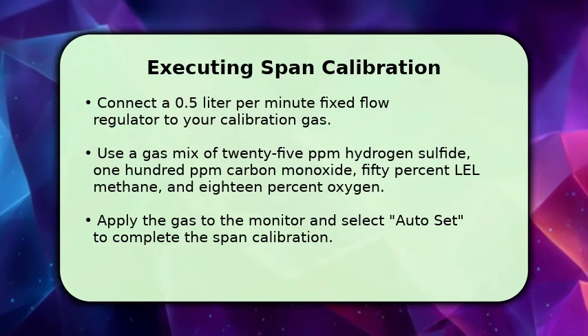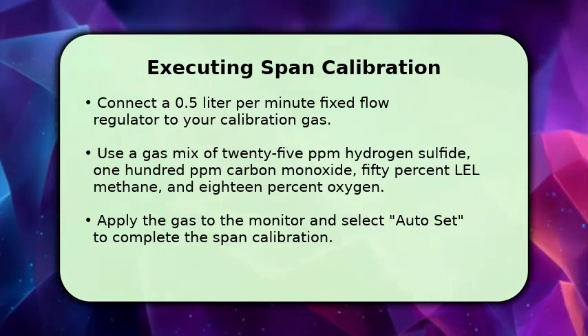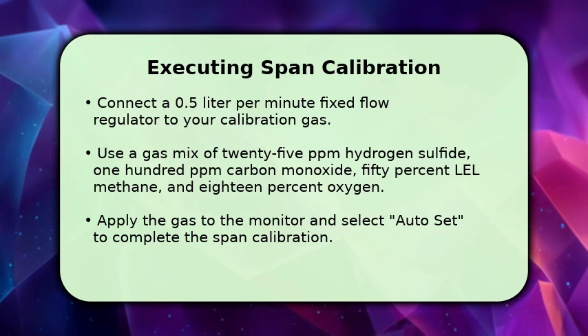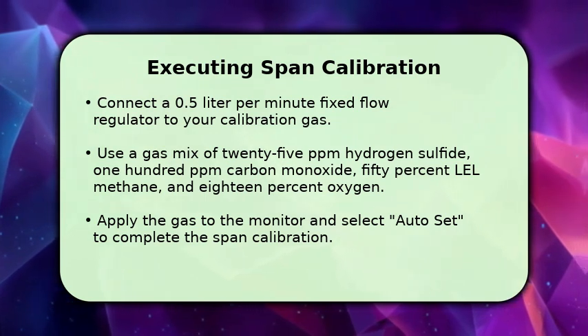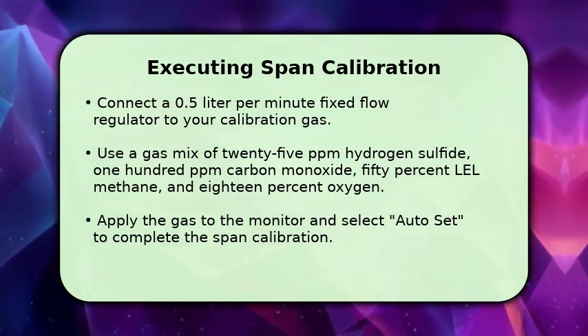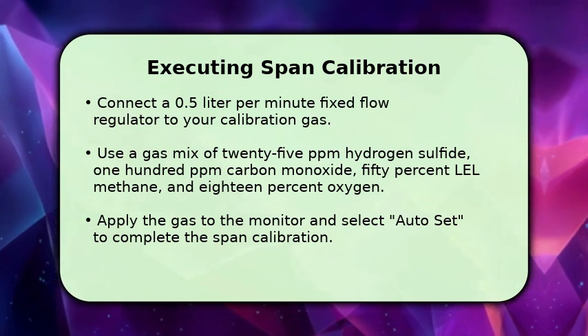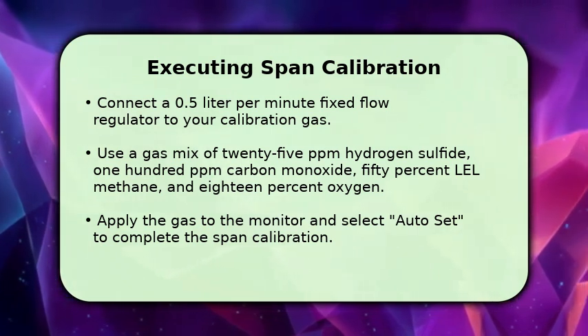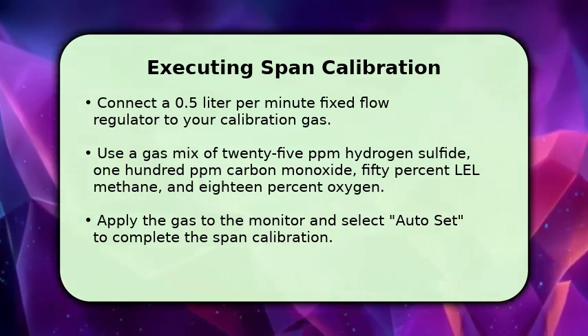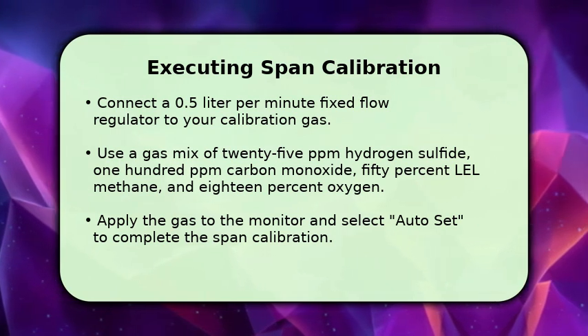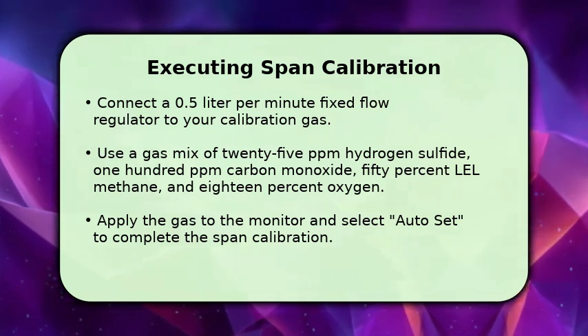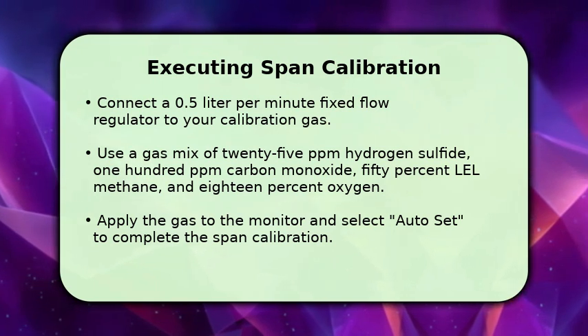Next, we move to span calibration. You will need a calibration gas cylinder and a 0.5 liter per minute fixed flow regulator with a C10 fitting. A typical gas mix contains 25 parts per million hydrogen sulfide, 100 parts per million carbon monoxide, 50% LEL methane, and 18% oxygen, with a nitrogen balance.